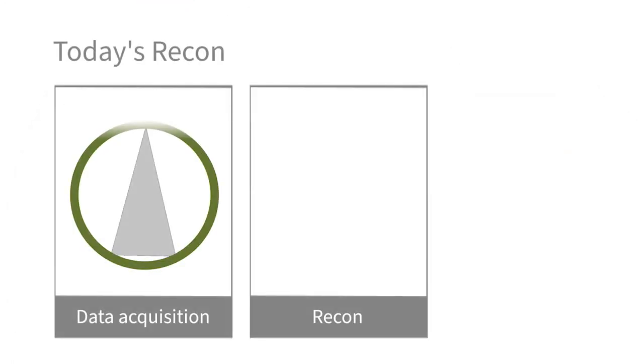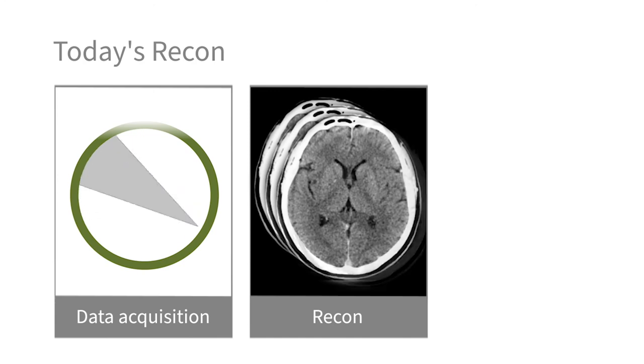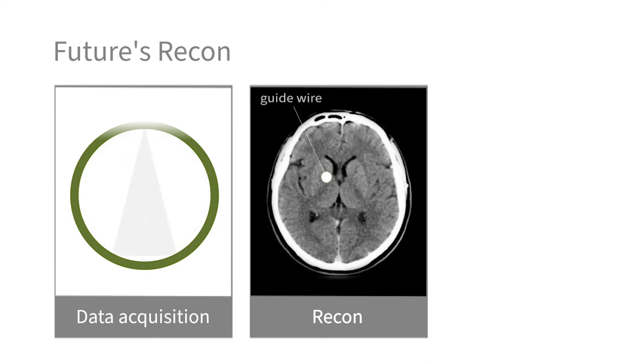To understand how this is possible, and why it does not provide an excessive dose to the patient, we have to take a deep dive into reconstruction algorithms. Today's reconstruction algorithms treat every projection independently from a projection acquired at an earlier time point. However, during interventions, the changes in volume being scanned are very sparse and follow certain rules. This fact can be exploited through methods such as compressed sensing or machine learning to significantly reduce radiation dose.